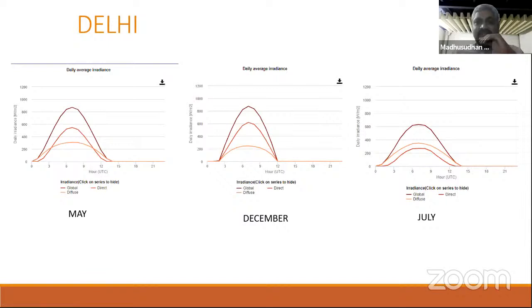Anybody going for solar thermal should actually test the microclimate in terms of the actual radiation available. Even large companies - those with 50 megawatts of solar thermal, and even a company with 2.5 megawatts - made this mistake where everything was designed on satellite data and ground data was not taken. When the system started, they realized there was a lot of dust, because of which the radiation shown here was not what they were actually getting on the ground. So you have to be really clear, especially with high temperature applications.